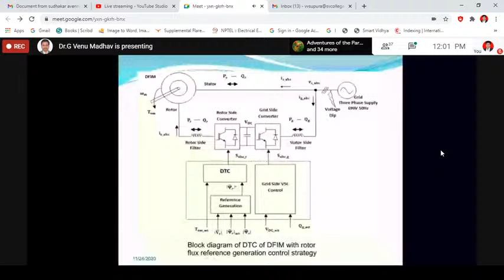If there is any fault on the rotor side converter, say a voltage dip, it will lead to heavy current in the rotor side converter, which may damage the AC/DC/AC converter totally. That should not happen, so we need to restrict it. We put down a crowbar resistance immediately, shrinking down with crowbar resistance and protecting the rotor side converter. At that instant, the grid side converter will act as a STATCOM, injecting reactive power so the voltage will be restored back to normal, without making the wind turbine stop. It will continue generating power if there is any fault on the system.